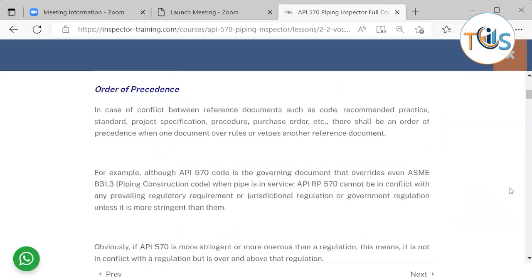Order of precedence means that in case of conflict between different reference documents — such as codes, recommended practices, standards, project specifications, procedures, or purchase orders — there should be an order of precedence when one document overrules or vetoes another reference document in case of contradiction between them. For example, API 570 code is the governing document that overrides ASME B31.3 piping construction code when pipe is in service.